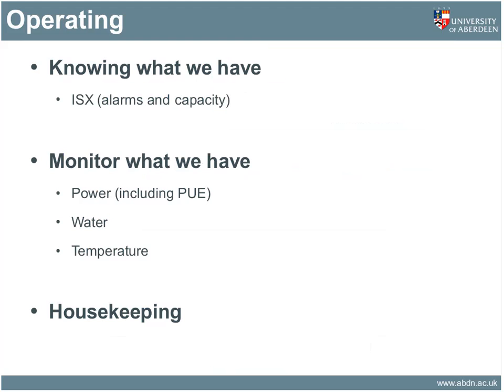The final part is, again, very much mirrored by what Steve was talking about. We now know what we have. We have monitoring for capacity and for alarms. Before we started this, we didn't have a good handle on exactly what we were running. We now monitor our PUE value very closely, as well as water usage, since we use a little water on the occasional hot day up here, and we monitor the temperature very closely within a number of parts of the data center.